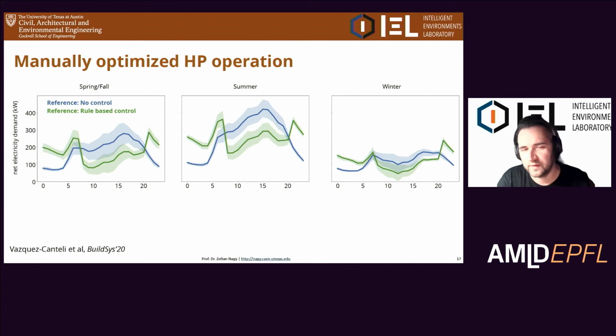Now, if you do what usually is done, and you take your heat pumps and you do a really good optimization, or you say, well, it's cheaper to do it at night, so we charge the storage at night, and then we release it during the day, which is kind of standard. So this shows you what you'd expect, right? The peaks will all move. You will get almost the same peak, just at a different time, which maybe is not what you're looking for. Essentially, by moving everything into the night, these are optimized to be done storing at like 7 a.m. in the morning, which is usually when you're switching tariffs also in the morning and the day. So basically, no reduction really on the peak, but a little bit on the conversion.